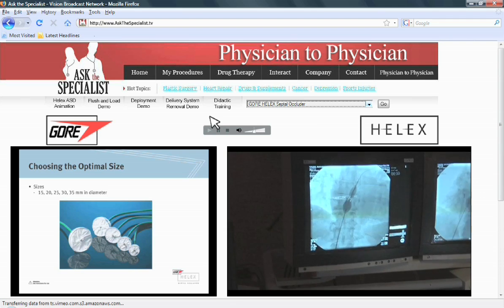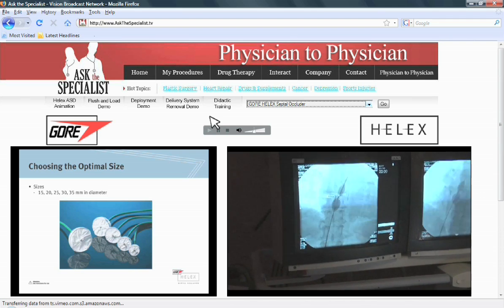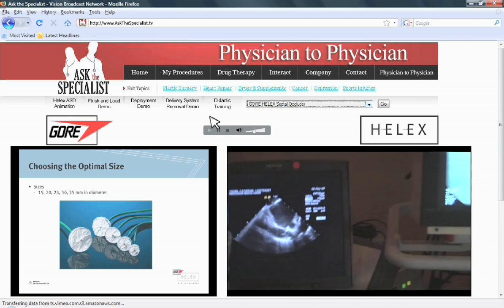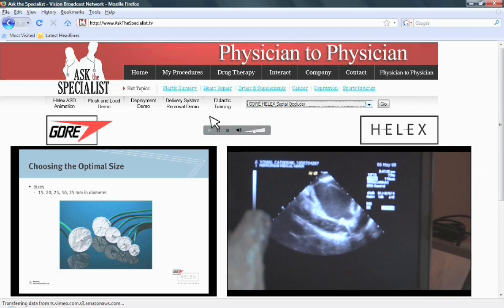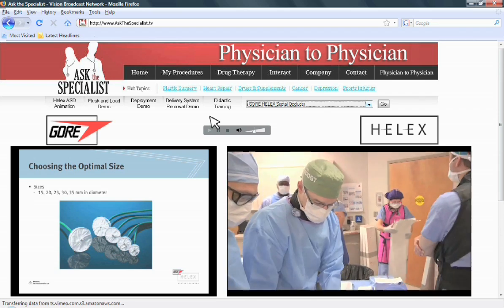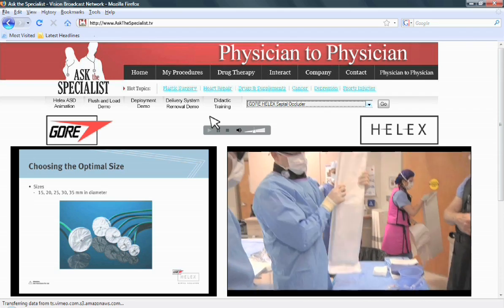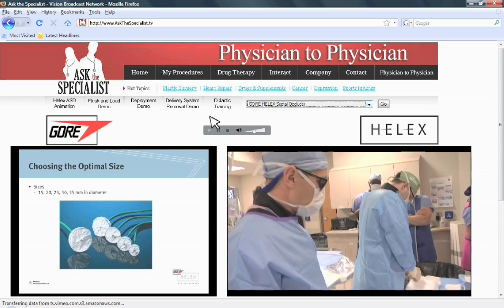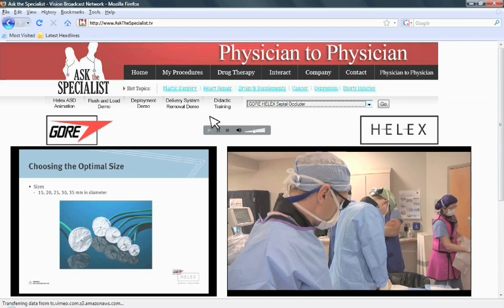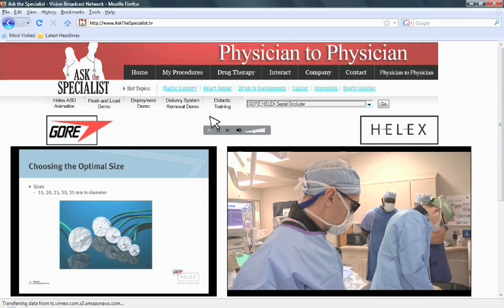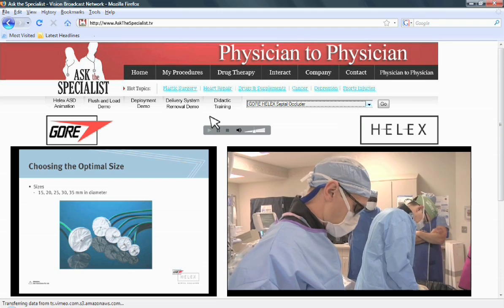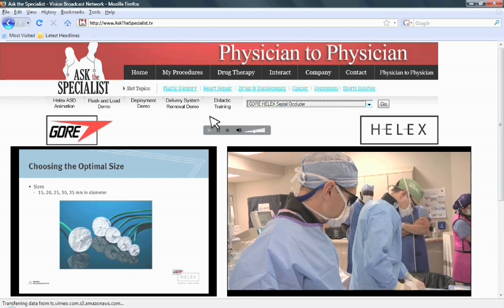We can size it on ultrasound, but we're just gonna go ahead and close it, because that looks visually about right. So you have to have a 2-to-1 ratio with the hole diameter and the device, so that would make it at least a 10. So I just chose to do the 20 millimeter device.